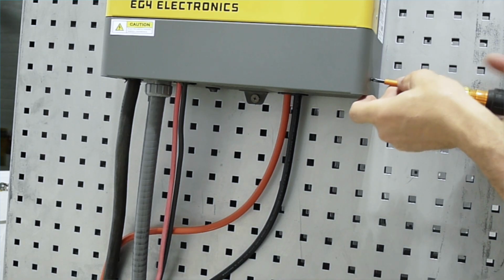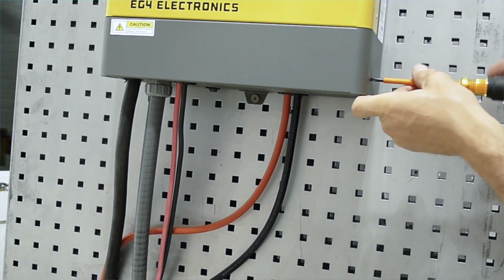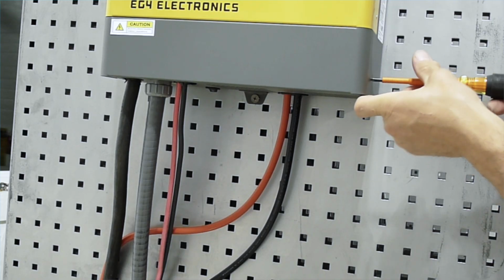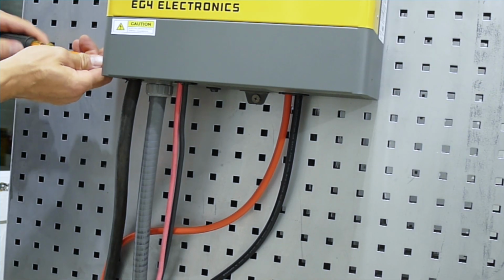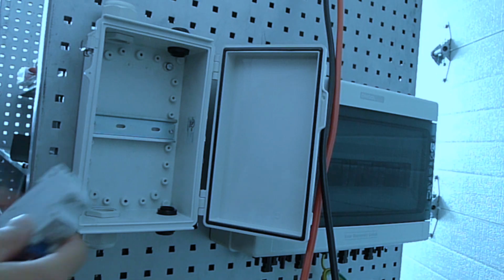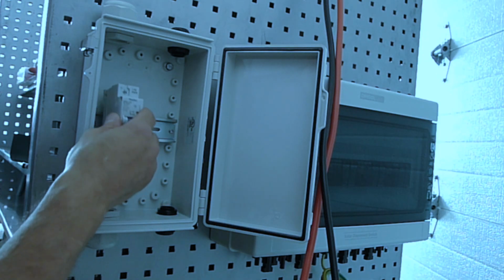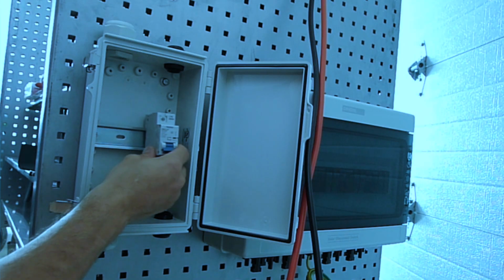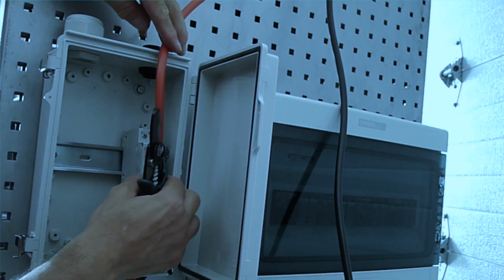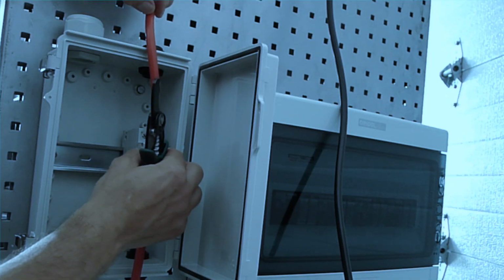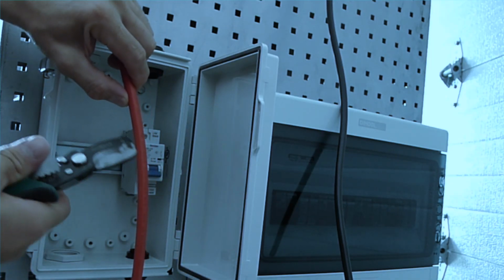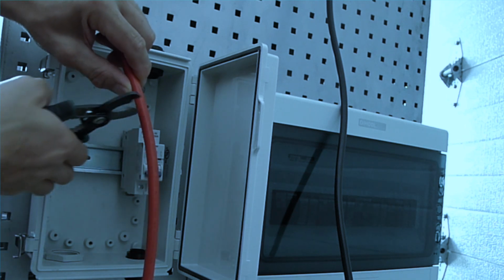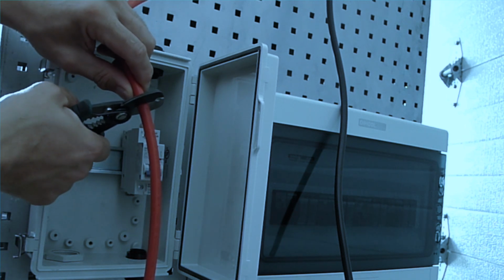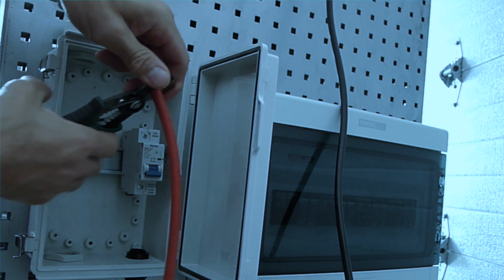We connected all the wires to this inverter. Now let's secure the cover back and install the 125 amp DC circuit breaker on the positive wire between the inverter and the battery. We can easily mount the breaker on the rail by pushing it on. After we measure out the length of the cable up to the breaker connection point, cut the cable, remove the insulation with the proper tool and secure it.